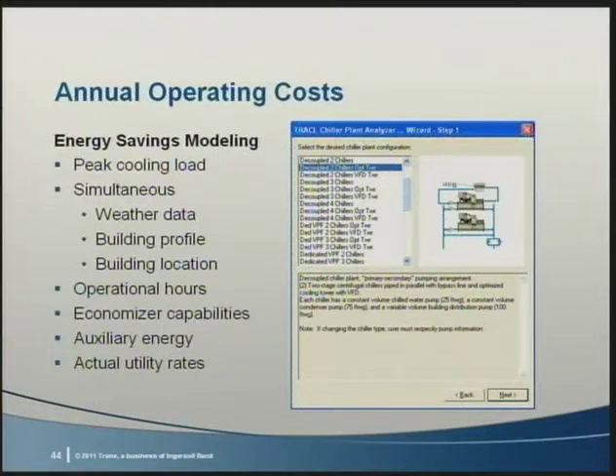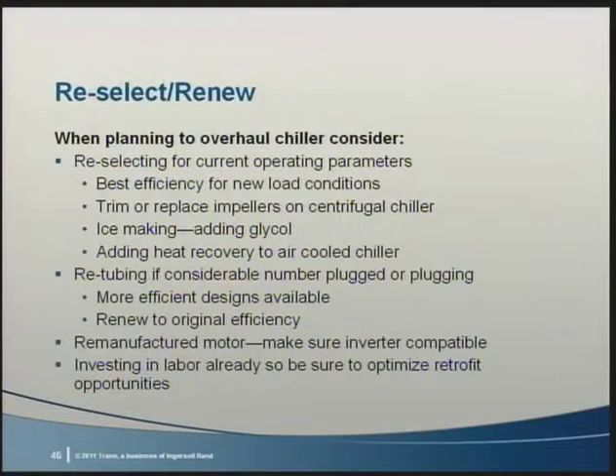Trane offers several tools that account for these factors and provide easy plant configuration comparisons. Now, there's a few other modifications worth mentioning. If you're already budgeting a chiller overhaul, consider what changes you can make to it to increase efficiency. You might trim or replace the impellers on a centrifugal, or add ice making to your screw chiller to take advantage of the chiller capacity available at night.